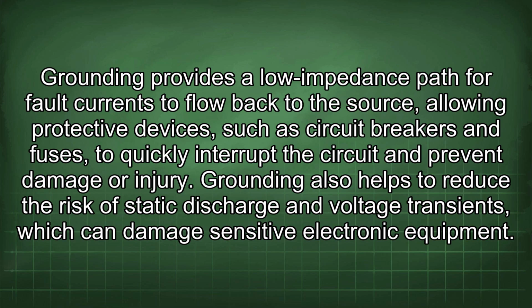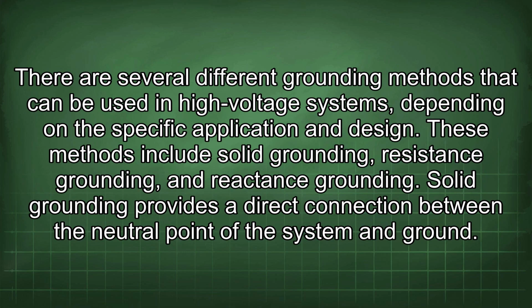Grounding provides a low-impedance path for fault currents to flow back to the source, allowing protective devices, such as circuit breakers and fuses, to quickly interrupt the circuit and prevent damage or injury. Grounding also helps to reduce the risk of static discharge and voltage transients, which can damage sensitive electronic equipment. There are several different grounding methods that can be used in high-voltage systems, depending on the specific application and design. These methods include solid grounding, resistance grounding, and reactance grounding.